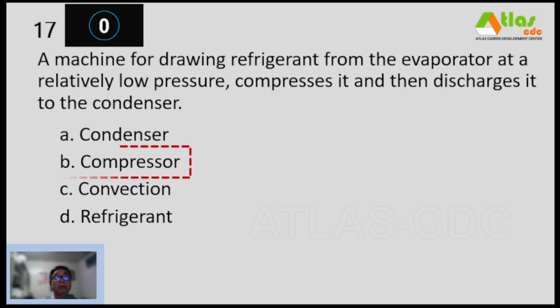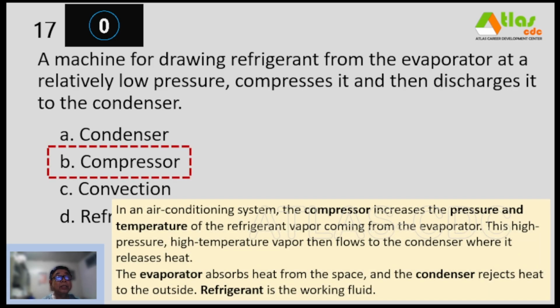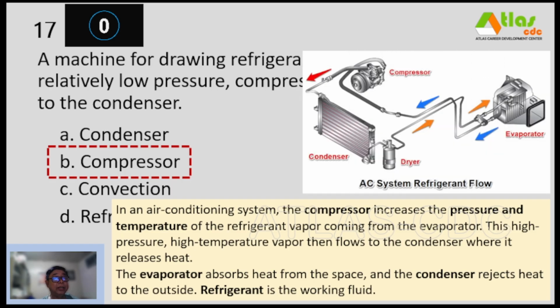And our correct answer is letter B, compressor. So in an air conditioning system, the compressor increases the pressure and temperature of the refrigerant vapor coming from the evaporator. This high pressure, high temperature vapor then flows to the condenser where it releases heat. So ito, pagdating dito, nilalabas yung init kaya sa condenser, yung nasa labas na unit ng split type, doon lumalabas ang mainit na hangin. The evaporator absorbs heat from the space and the condenser rejects heat to the outside. Refrigerant is the working fluid.